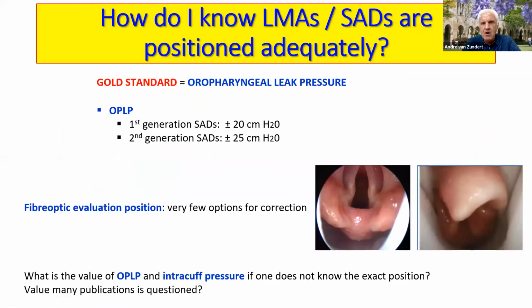And why is that necessary? How do I know that the device sits correctly? Thus far, with the blind insertion technique, the gold standard is the use of the oropharyngeal leak pressure, which for first generation is about 20 centimeters of water. For second generation, it's about 25 centimeters of water. And then you have the fiber optic evaluation, and you see good views or less than optimal views with a fiber optic scope. But that does not allow you to do any corrections of any of the malpositioning. So that is good. It's expensive, but it does not allow you to do any correction of the insertion.